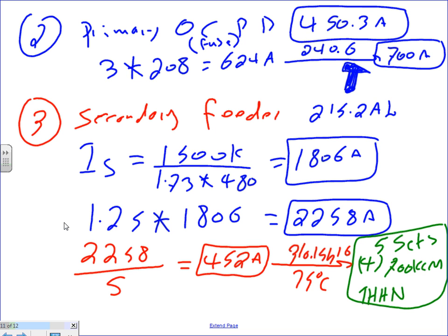Can I go to the fourth, guys, to find the overcurrent picture? Yes, sir. Who decides the size of the transformer? Well, ultimately, there are two types of transformers. One, you own and operate in your building, and one, the utility owns and operates outside. If it's the utility transformer, they decide it. If it's your transformer inside your building to take the 480 to 208, you decide it. How do you size it?